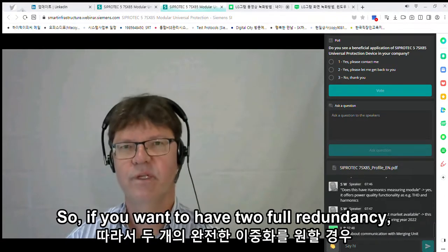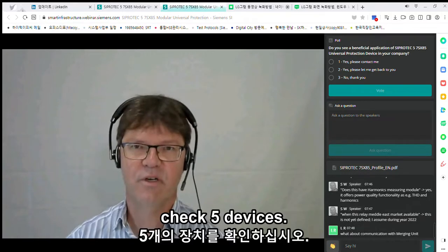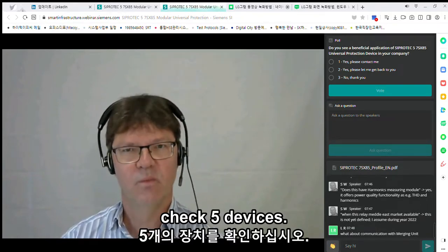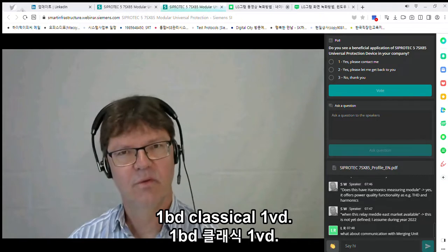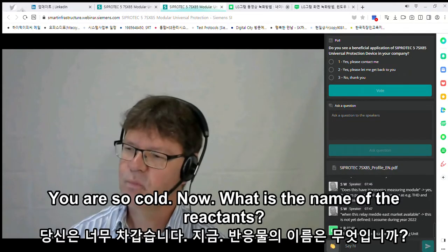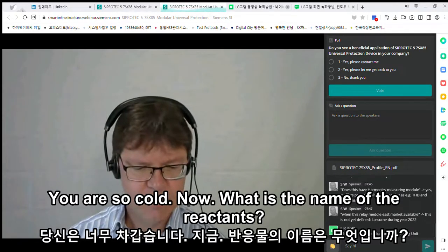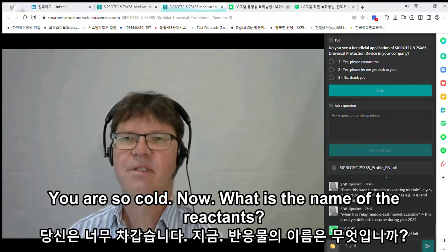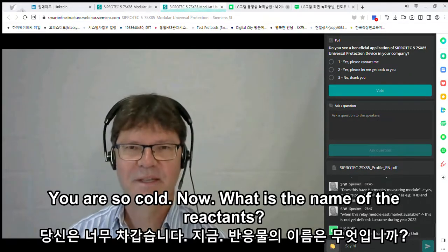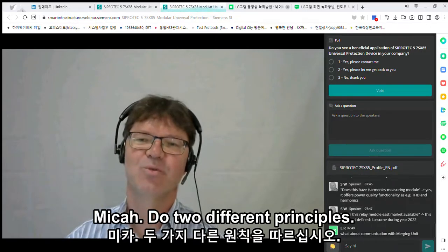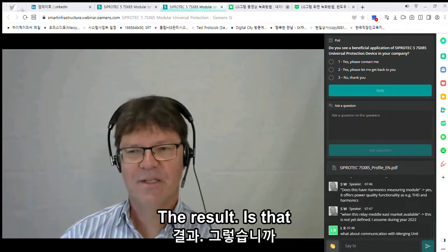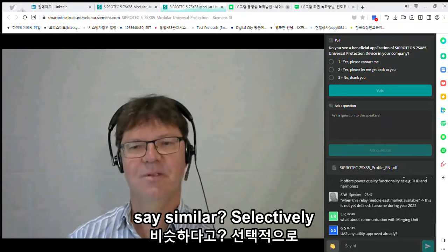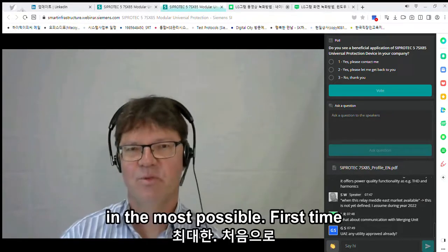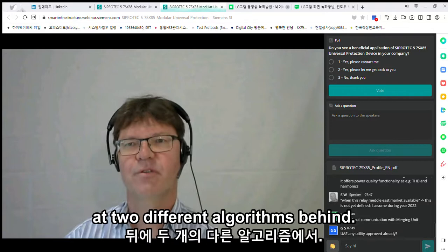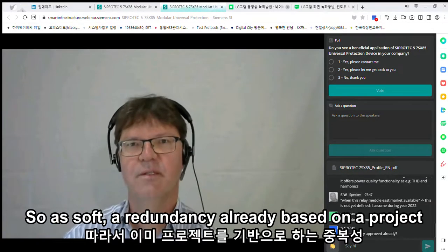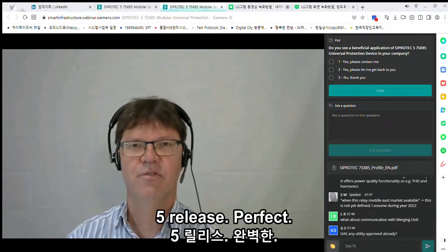So if you want to have the full redundancy, you can take 2 SIPROTEC 5 devices, one with the classical, one with the newer so-called, now what is the name? Reactance method. Reactance method distance protection, RMD it is called. Yeah, thank you, Michael. So 2 different principles. The result is, let's say, similar, to trip selectively in the fastest possible time, but 2 different algorithms behind. So a software redundancy already based on SIPROTEC 5 relays.